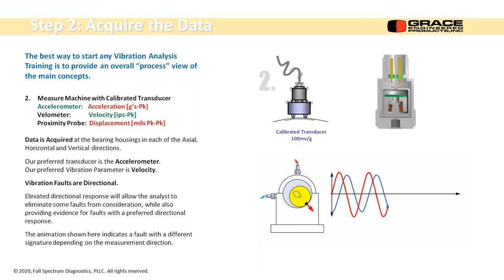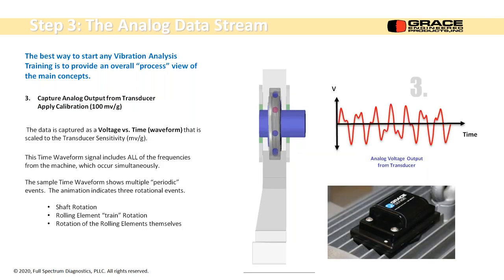Thankfully, a lot of transducers now are triaxial, and that MEMS accelerometer is also triaxial. So we'll pick up all three directions simultaneously. What do we get? We get an analog waveform. This is voltage versus time until we put in that 100 millivolt per G calibration factor. What we're seeing is all the vibration in the system.